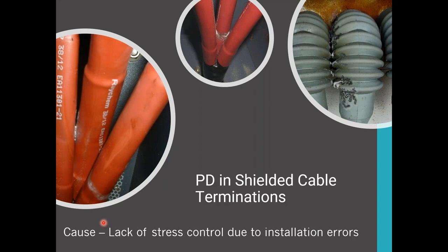Some more cables. The shield was cut back on them, but it was cut back too low. You can see the cables of different phases coming into close proximity in an area that's not shielded. That created an electrical stress point between them, and there's that white ash of the breakdown of the insulation. Over time, this would have flashed phase to phase.